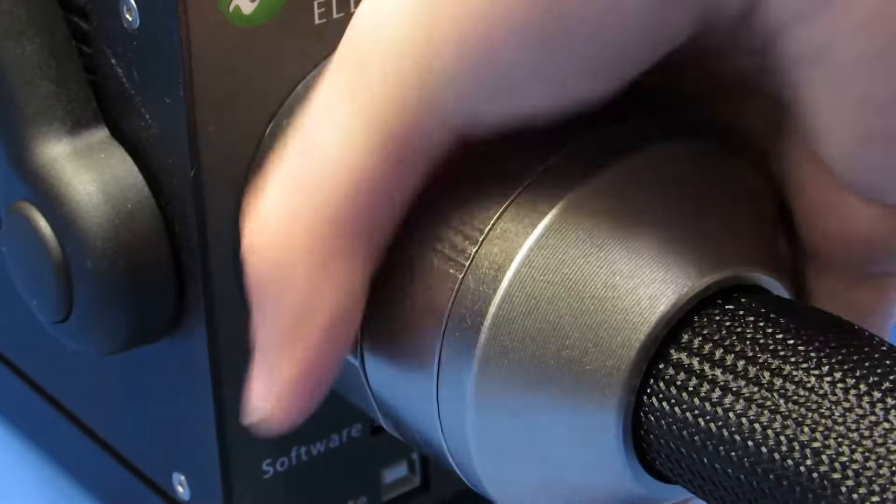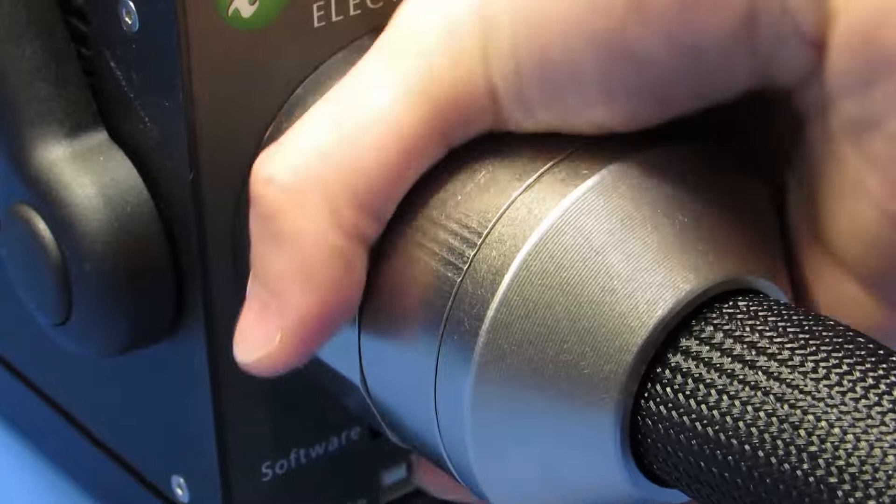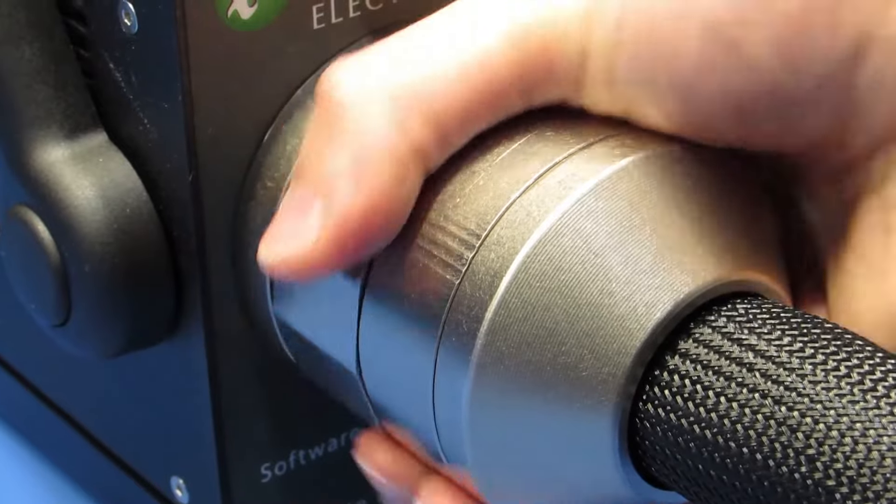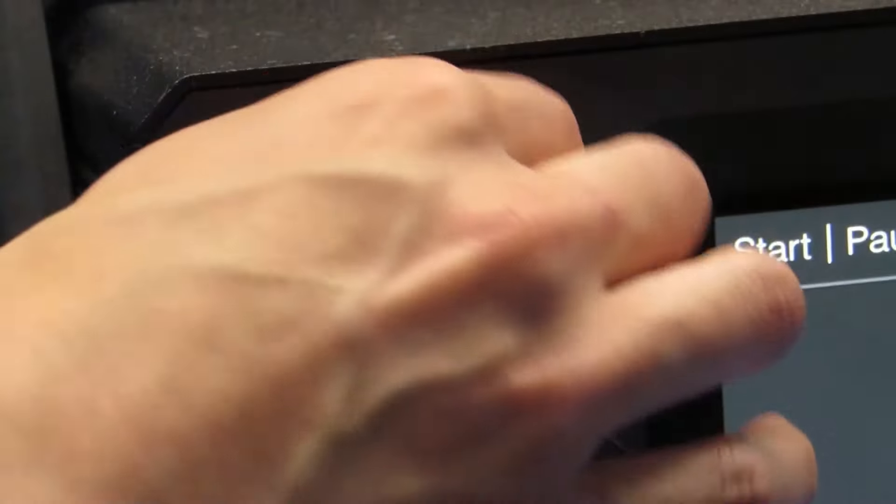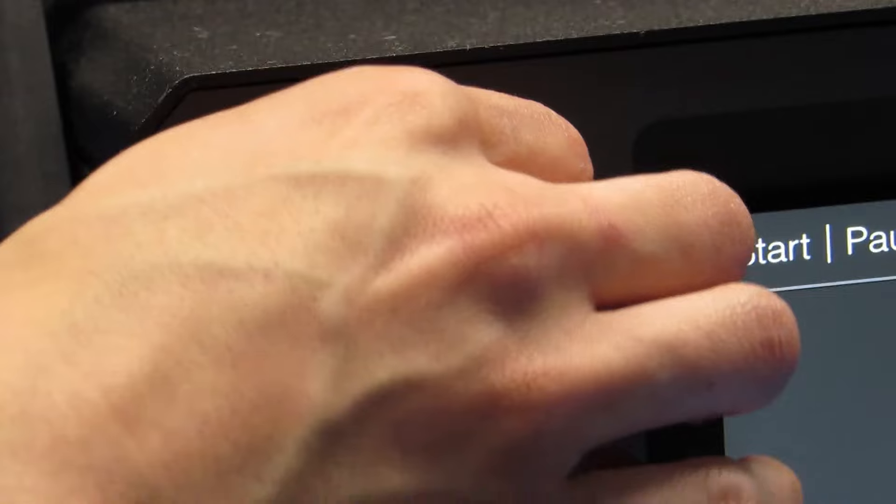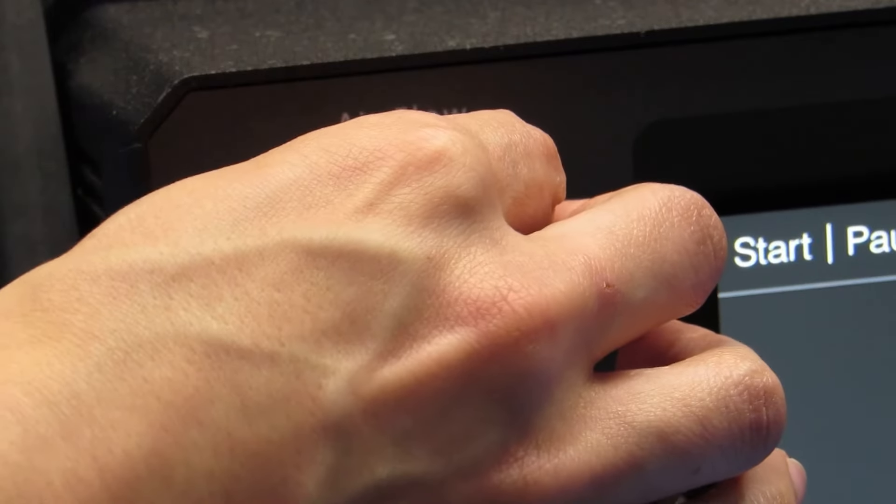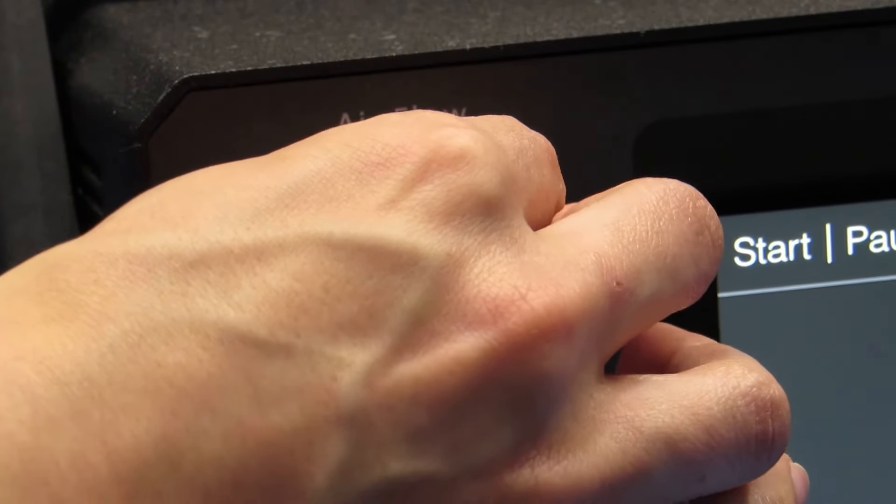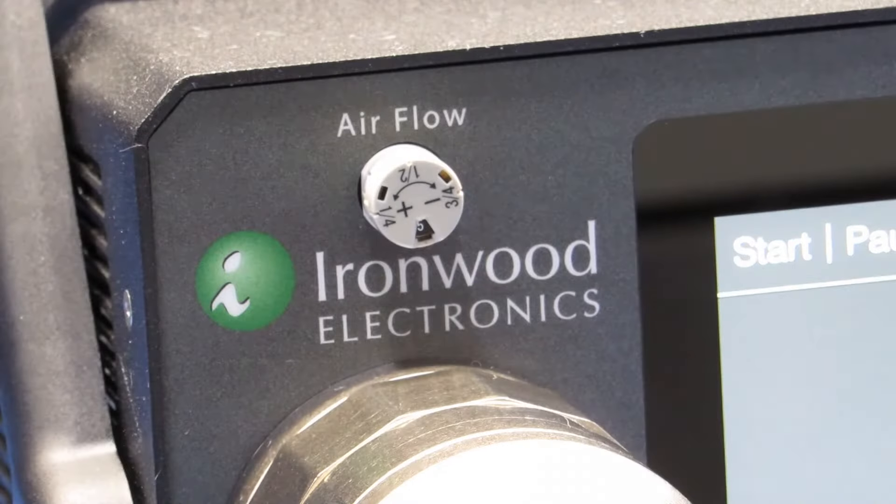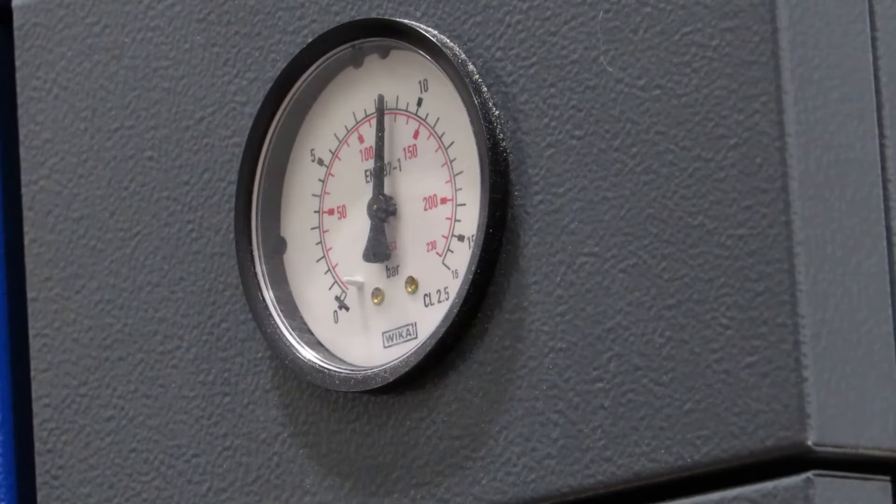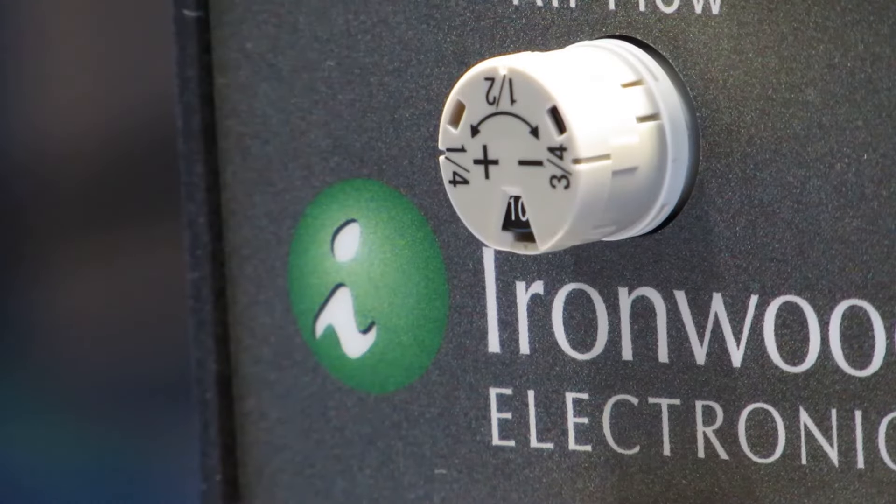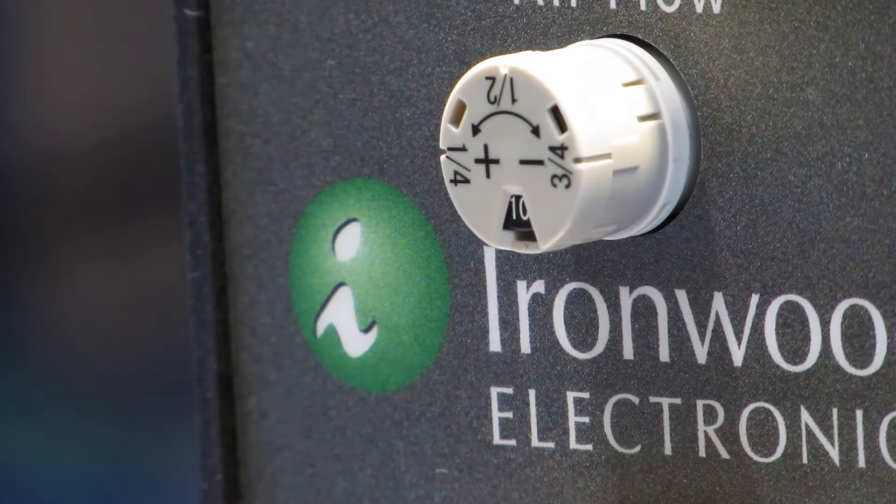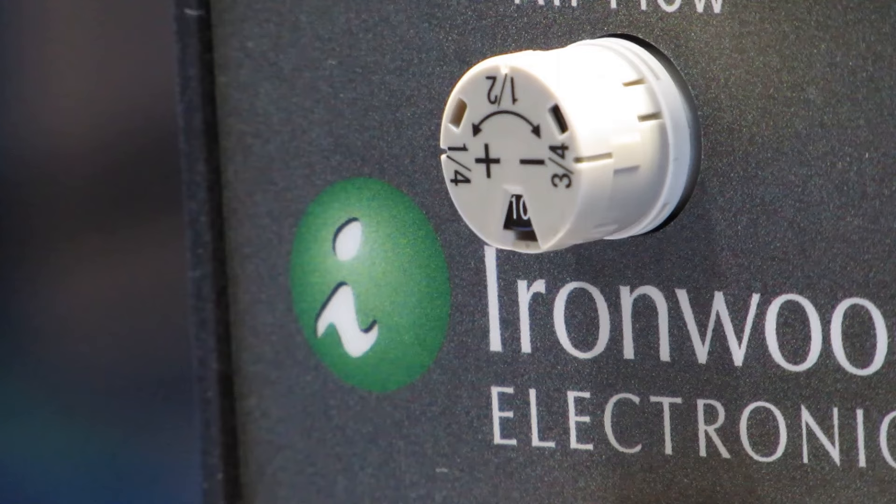Once it comes to a stop, the thermal head is connected. Set the dry air supply to a value of five. If condensation is still formed on the test fixture, check that the dry air supply is rated for a dew point of negative 55 degrees Celsius. If this is confirmed, increase the airflow by quarter turn increments until condensation no longer forms.